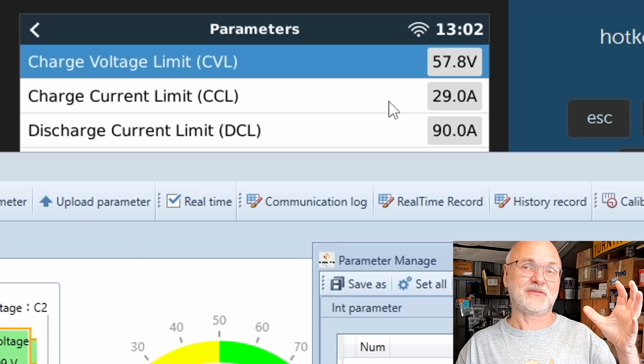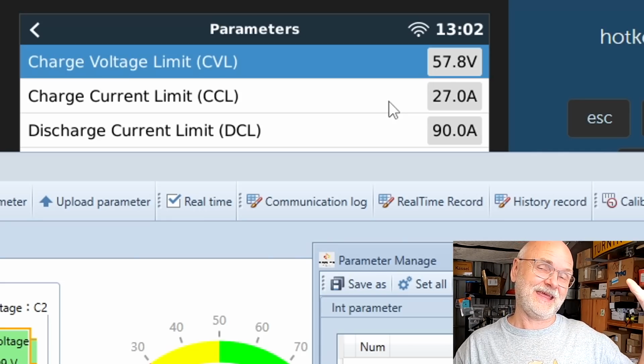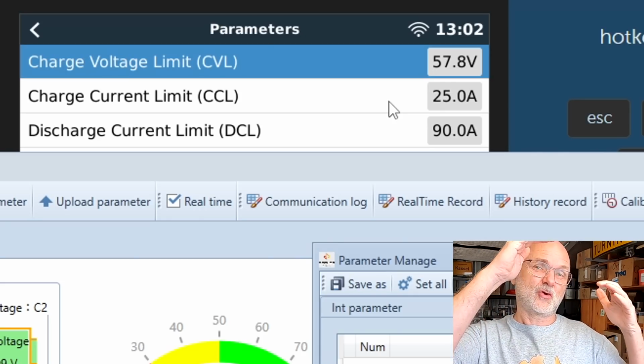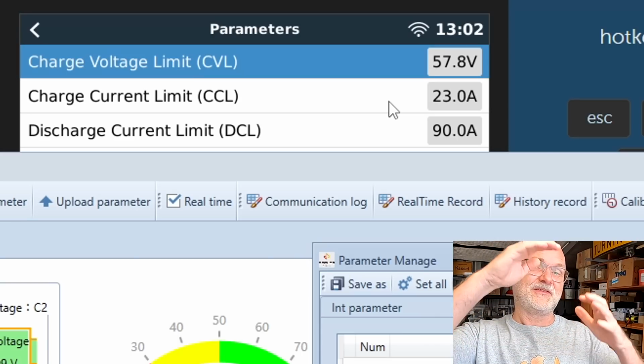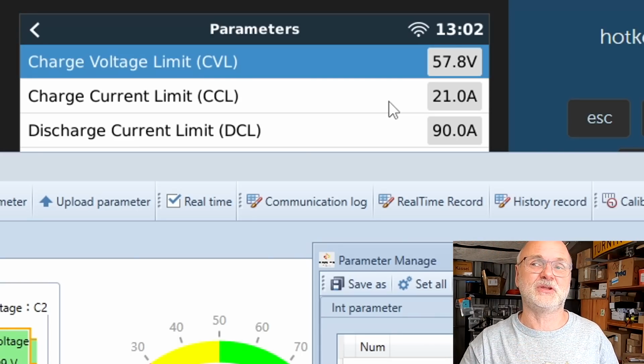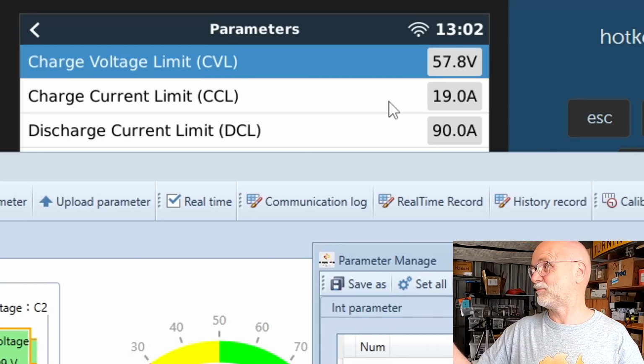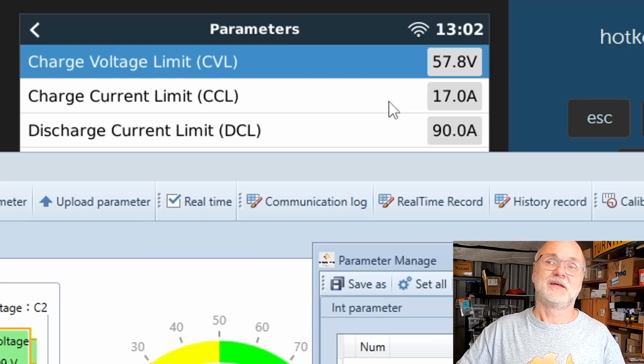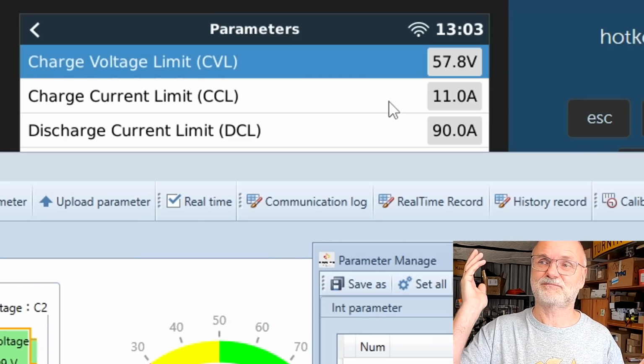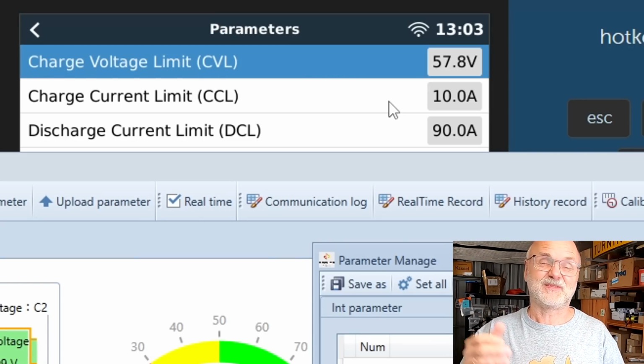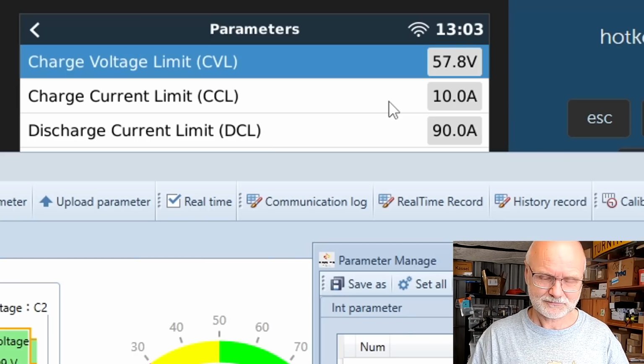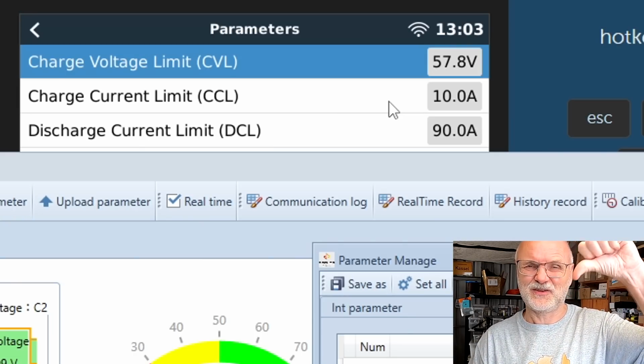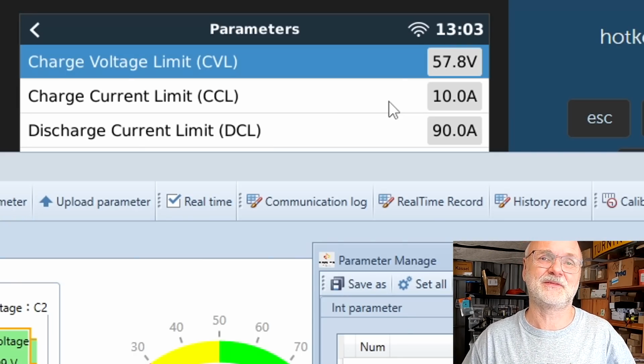Any loads connected to the system which need more power take the energy from the battery, so you're constantly discharging and charging, cycling your battery at this voltage, which I don't like. We've got plenty of sunshine outside now, so the charge controllers could deliver like 10 kilowatts or more, but instead I'm discharging my battery. This was always a big negative point in the Seplos BMSs.